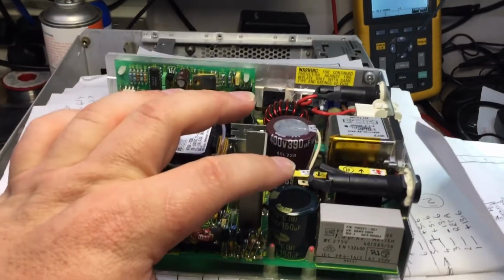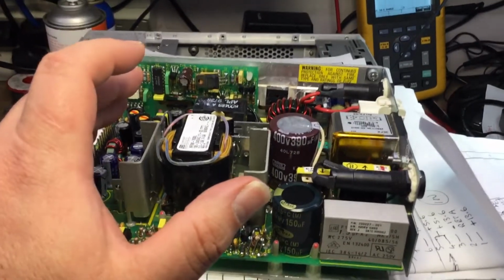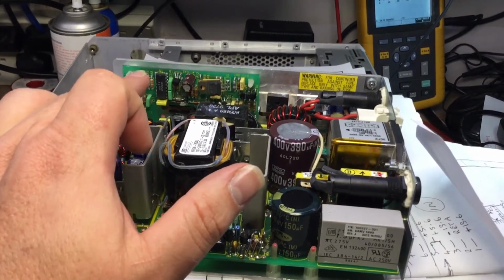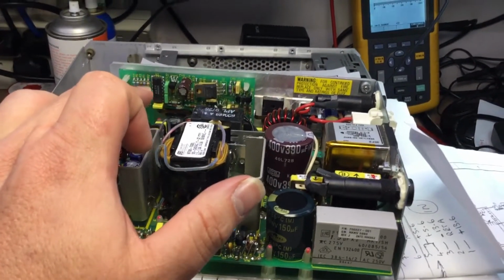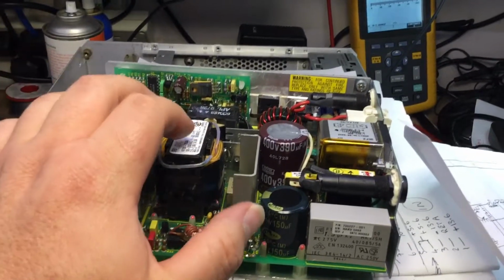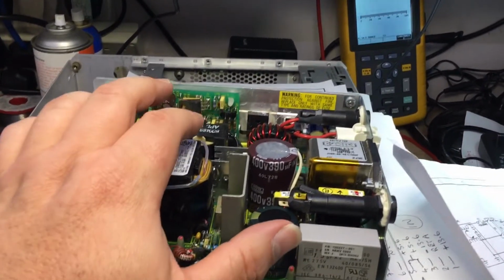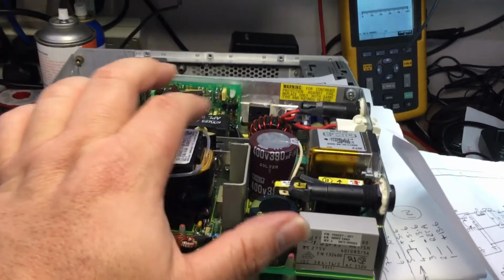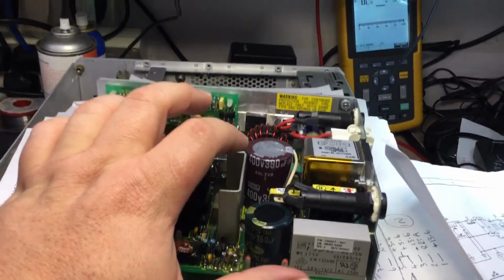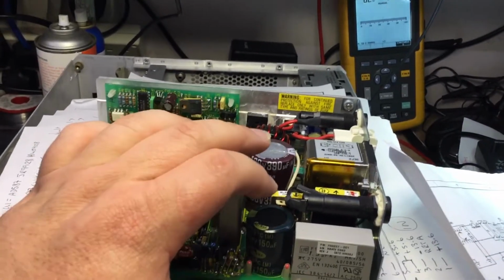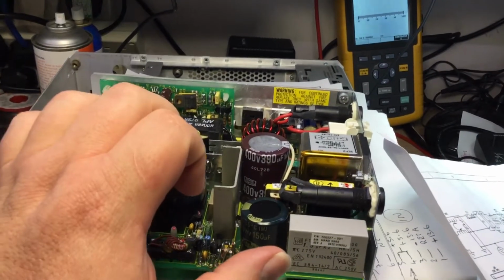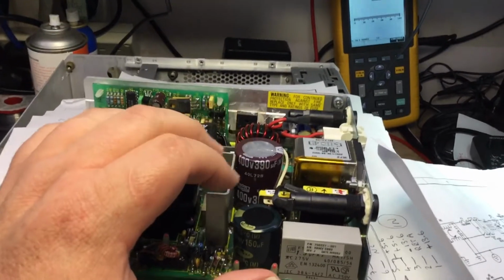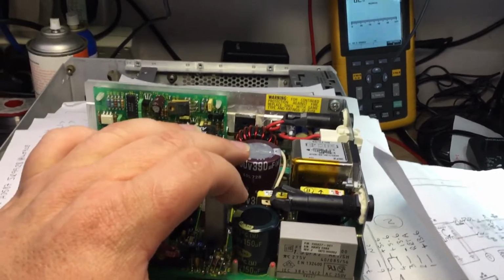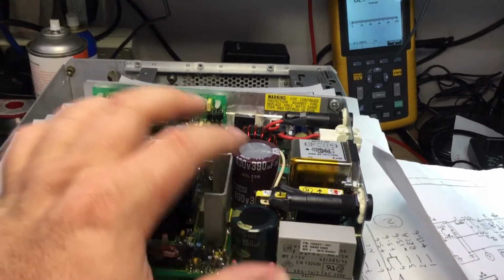Whenever there's a current draw on the output, the DC control board monitors a 5-volt rail, and if it sees that the 5-volt output leaving the supply has dropped, it will increase the current drive to this transformer to compensate for the DC fall on these two reservoir caps, boosting them up higher, because it doesn't take much current draw to reduce the voltage on these capacitors since it's quite a low current drive. Anyway, that's my theory of it.